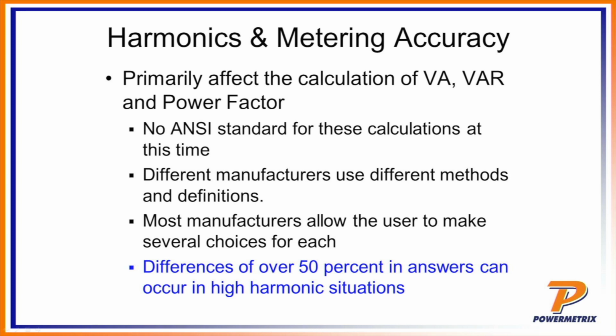All right, so next thing. Mentioned before, there is not a standard calculation right now for that, but the ANSI committee is working on that. We did do some experiments. A couple other manufacturers have done experiments and found, historically speaking, older meters can have up to 50% difference in their answers for the same harmonic waveform when running on VA or VAR metering.